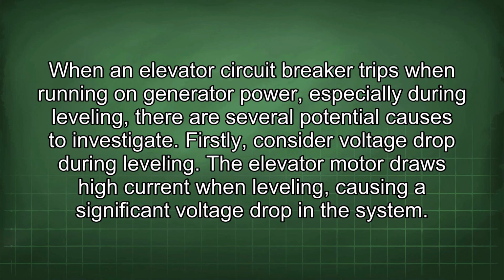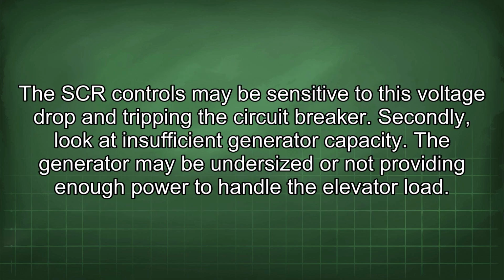When an elevator circuit breaker trips when running on generator power, especially during leveling, there are several potential causes to investigate. Firstly, consider voltage drop during leveling. The elevator motor draws high current when leveling, causing a significant voltage drop in the system. The SCR controls may be sensitive to this voltage drop, tripping the circuit breaker.